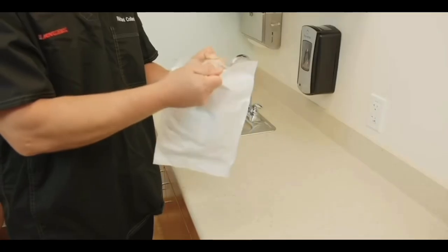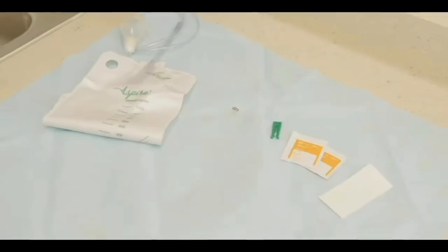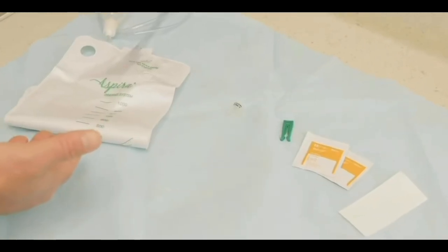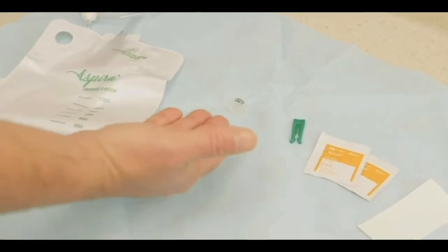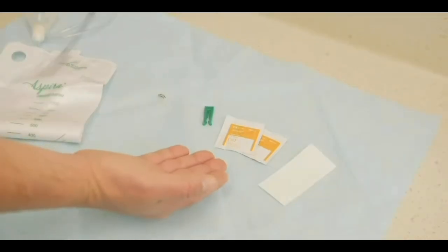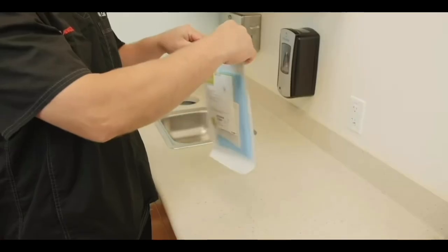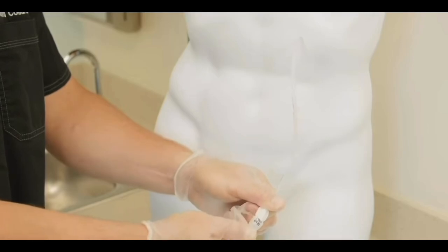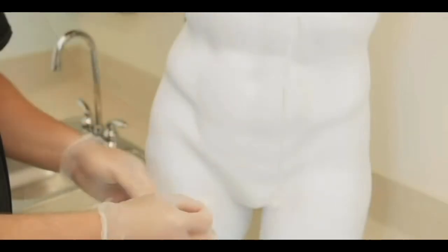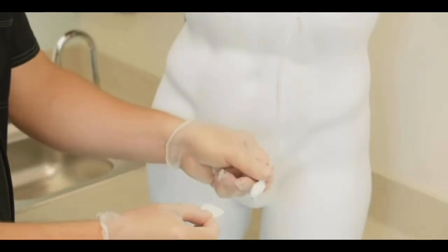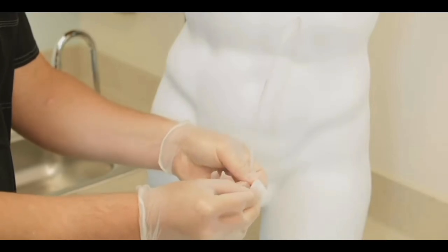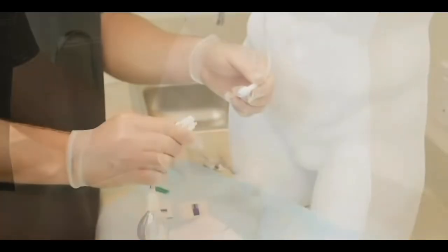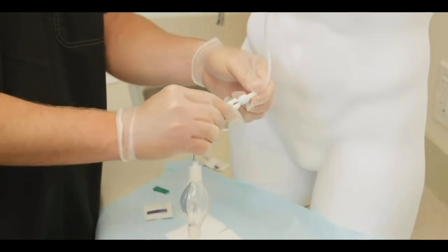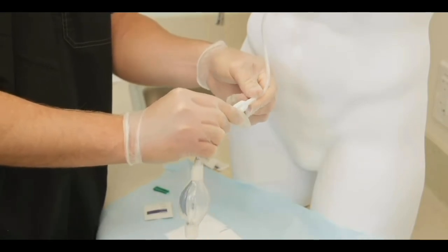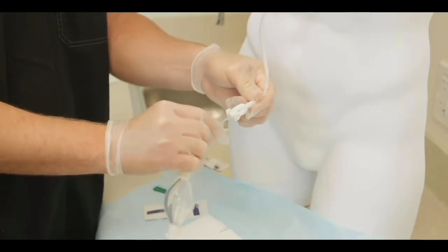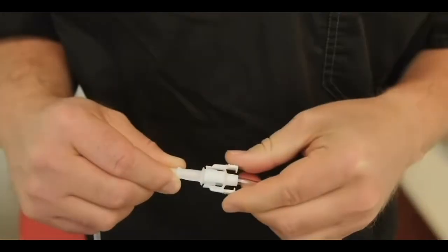To begin the drainage process, you will need the following supplies: the Aspira drainage kit, which includes the drainage bag, the catheter valve cap, an emergency catheter clamp, alcohol pads, and tape. After you have removed the valve cap, open the drainage kit pouch. Next, wipe the end of the valve with an alcohol pad. Pick up the connection end of the drainage bag and push it onto the end of the catheter until you hear or feel a click. Gently tug on the drainage line to make sure the connection is secured.